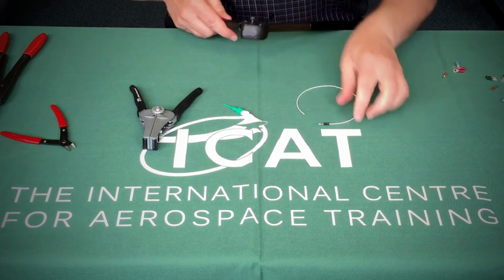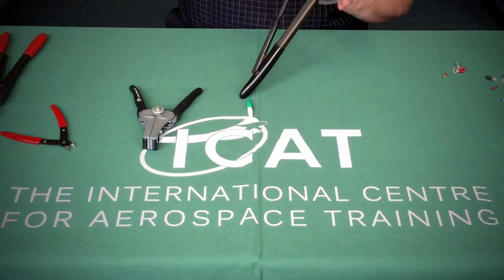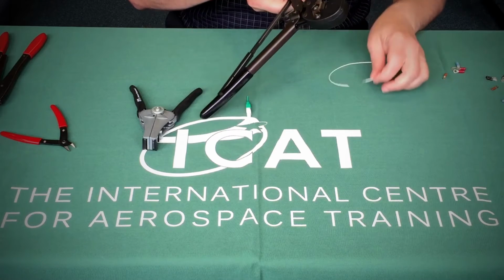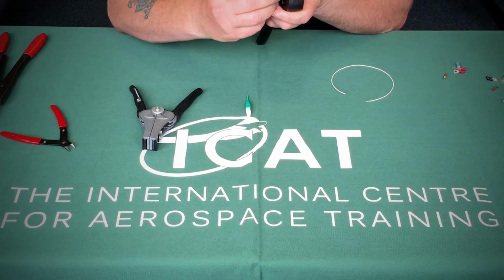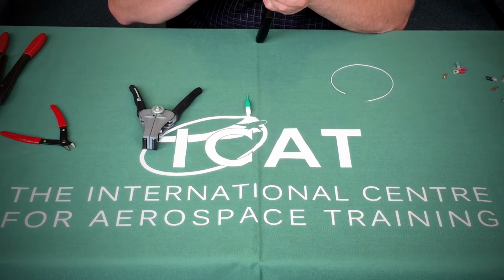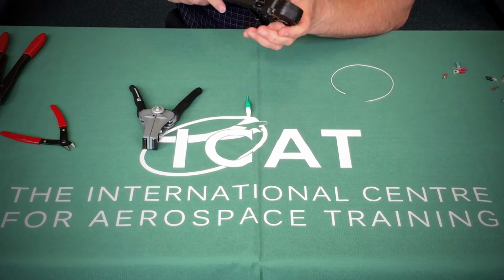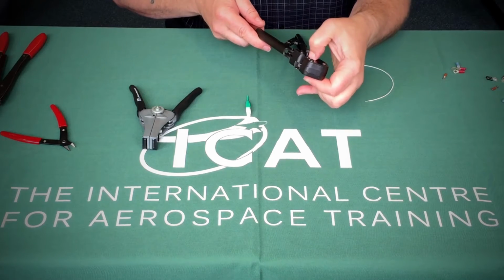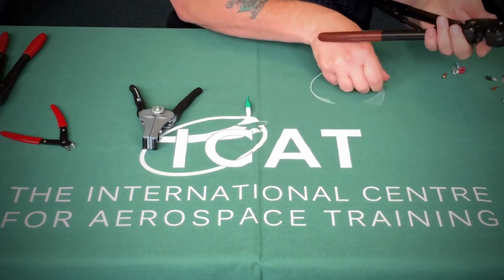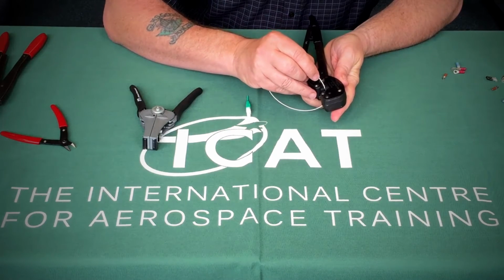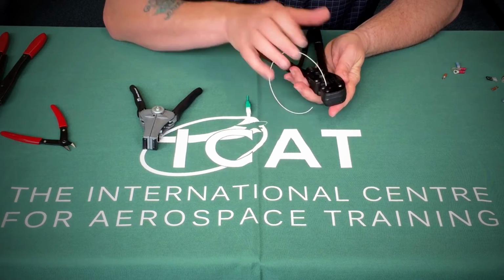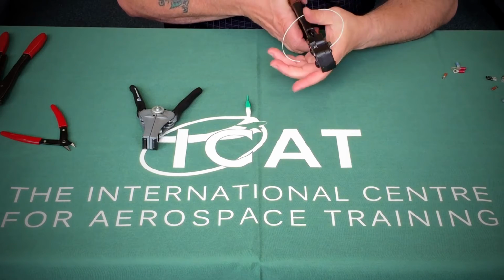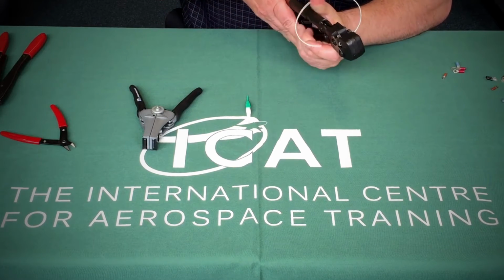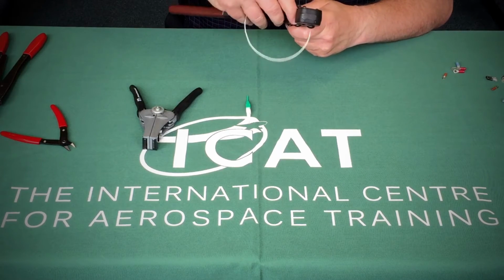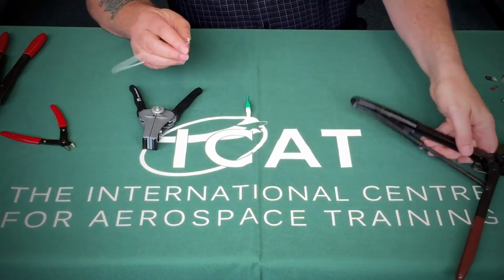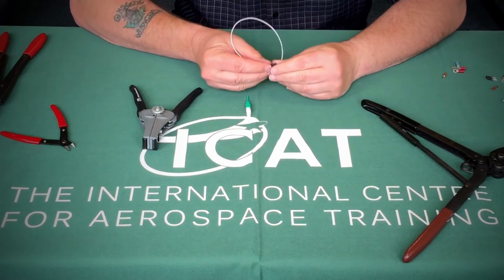Once again, open the jaws, and again, a little bit fiddly. Sometimes it's easier with the wire on, sometimes with the wire off. Fit the crimp into the crimp tool, and again, close the barrel up slightly. Now we've done that, I can look at my stripped wire and push him into the crimp itself. I'll now complete the crimp using the tool appropriately, remove the crimp from the tool and inspect it.